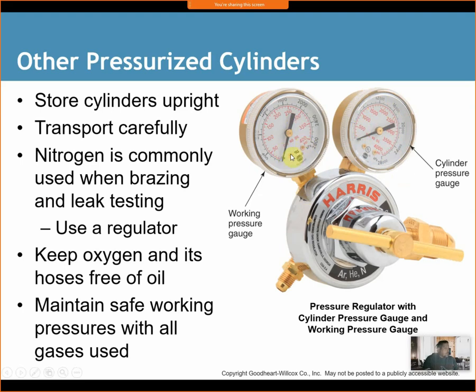This is the pressure we're going to set it to. So for example, if I'm leak testing a system, I'm going to set the dial to 150, and let my refrigerant or nitrogen flow through here into the system until it reaches 150. Pressure wants to equalize, so it's going to go from the tank into the system, and it's going to keep flowing until both the tank and this pressure regulator meet the desired pressure.